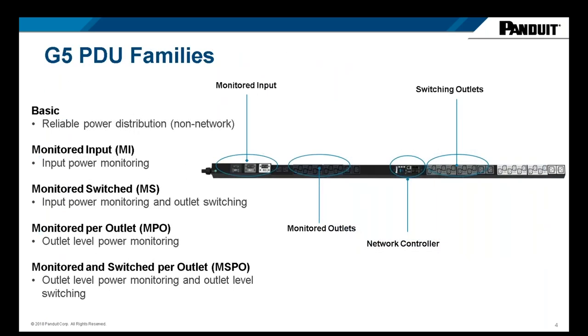Before we get into the nuts and bolts of the Gen 5 PDU, I'd like to do the anatomy of a PDU, if you will, and the different types of PDUs in the Panduit SmartZone G5 PDU family. We have a full line of basic PDUs - highly reliable, high quality. You get the outlet density, you get all the different input plugs, however you don't get a network card. So where you see on screen it says network controller, that's the main difference between a basic PDU and any of the intelligent PDUs.